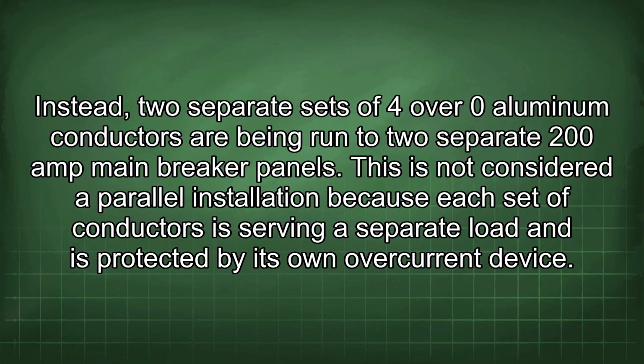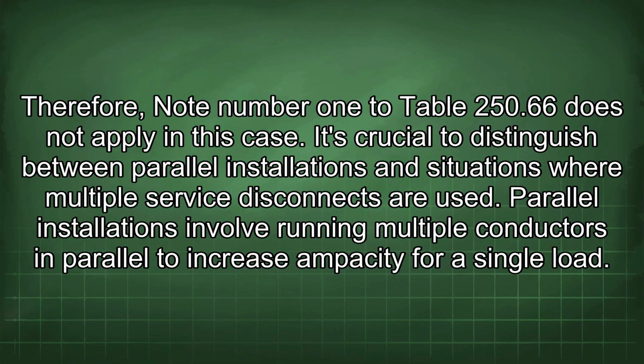Instead, 2 separate sets of 4/0 aluminum conductors are being run to 2 separate 200 amp main breaker panels. This is not considered a parallel installation because each set of conductors is serving a separate load and is protected by its own overcurrent device. Therefore, note number 1 to Table 250.66 does not apply in this case.